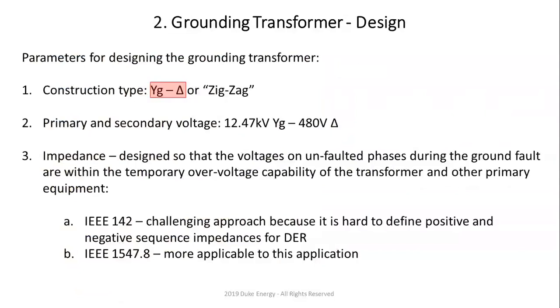So what happens essentially is that the grounding transformer you have here will have to be designed, right? You have two construction types: wye-grounded delta or zigzag. It's a personal or engineering preference. The reason why I picked the wye-grounded delta transformer is because we already had it in the standard. You can pick zigzag. On average, it's about 1/√3 smaller size-wise. But it's up to the engineer to pick one, right?